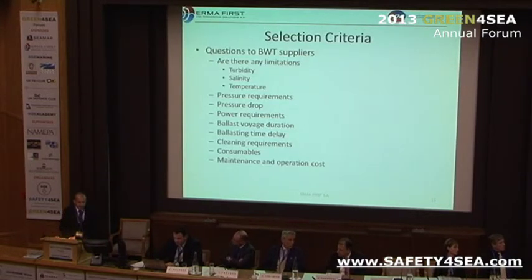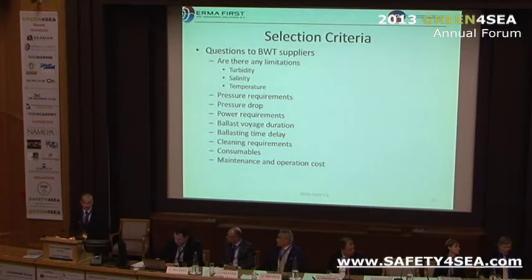And then specific questions to the suppliers. Are there any limitations for the operation of the systems, like water turbidity? There are some technologies that are really affected by water turbidity, and no matter how fine a filtration you're using, when the water is really turbid, the system is not operating efficiently. Salinity. There are systems in the market that have restrictions on salinity. Of course, there are different types of systems which can operate in a wide range of salinities, but still, salinity is an issue. Temperature, another issue.